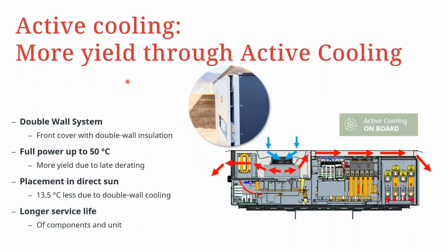AC isolator. Active cooling is also employed in the Tauro inverters, and it offers even more benefits because it has a double wall design, meaning that even when it's operating at 50 degrees ambient temperature, the electronics inside are at about 13.5 degrees less temperature because of this concept. So you can see where the cold air is being taken in from the inverter, and then it's being reticulated over the outer wall, and this is also helping a lot to keep the inverter components inside very cool.